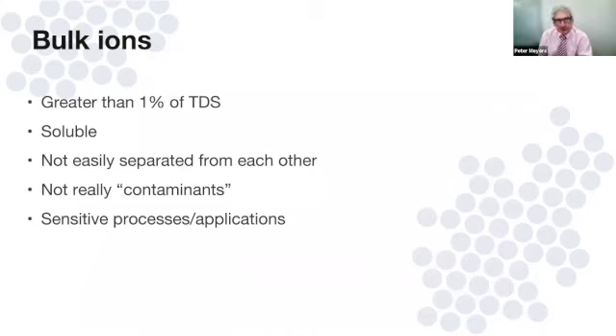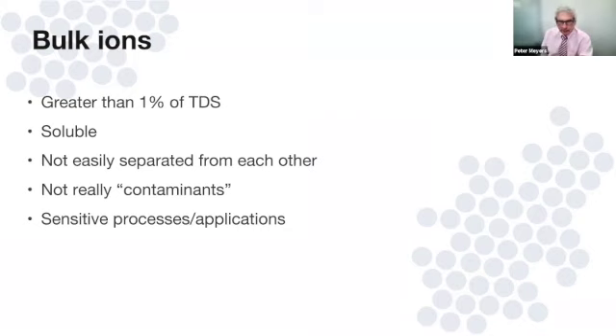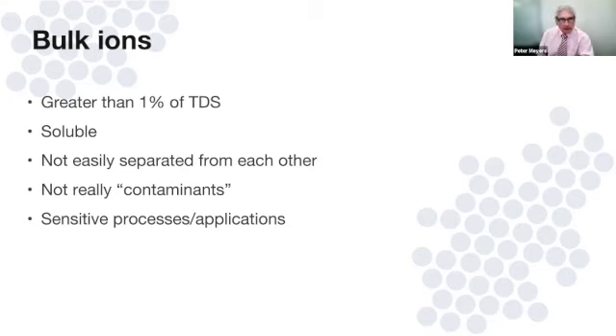Bulk ions are defined as being greater than one percent of TDS — trace ions, as covered in the previous webinar, are less than one percent. Bulk ions are generally very soluble, not easily separated from each other, and they're not really contaminants; they're the constituents, the salts you typically find in almost every natural water supply. On the cation side, the four most common bulk ions are sodium, potassium, calcium, and magnesium.